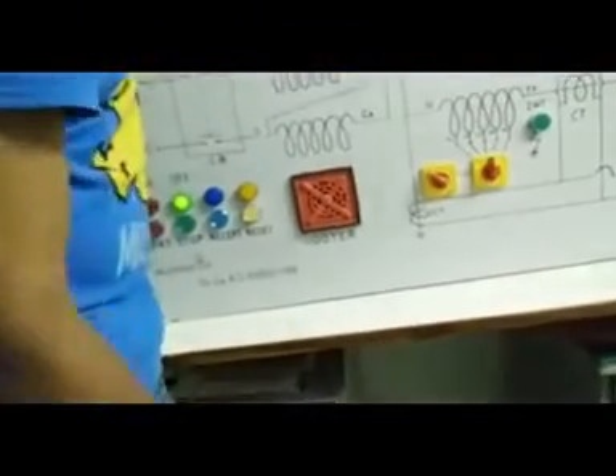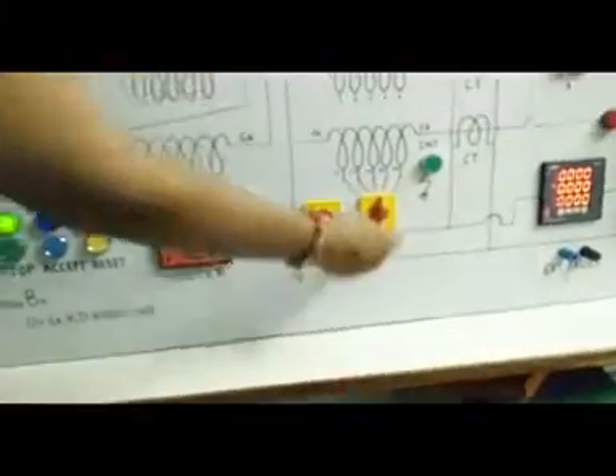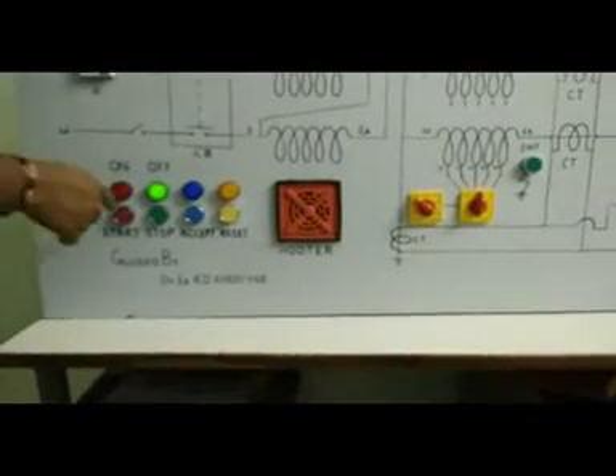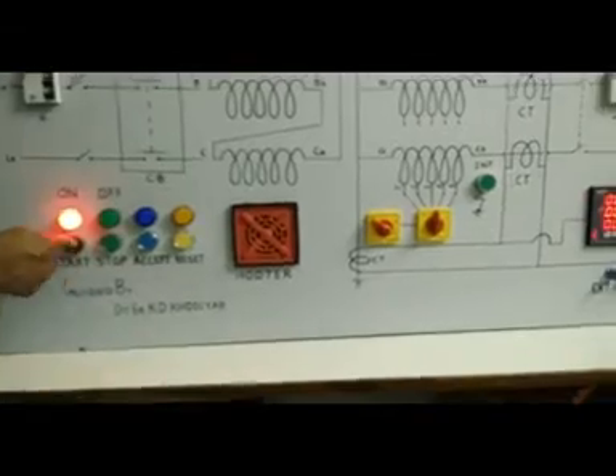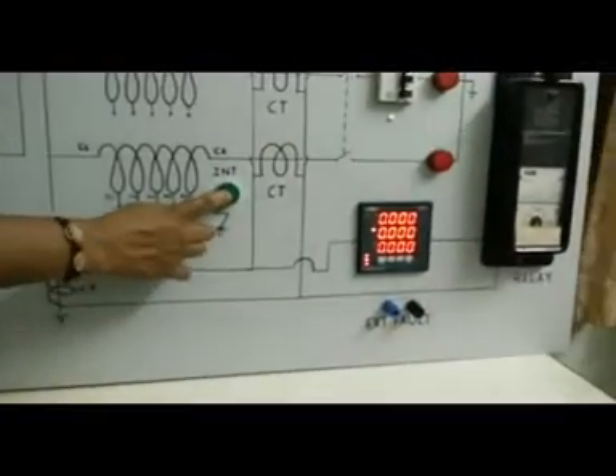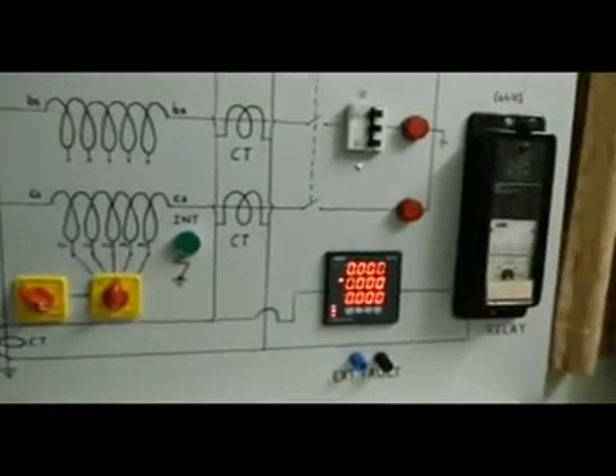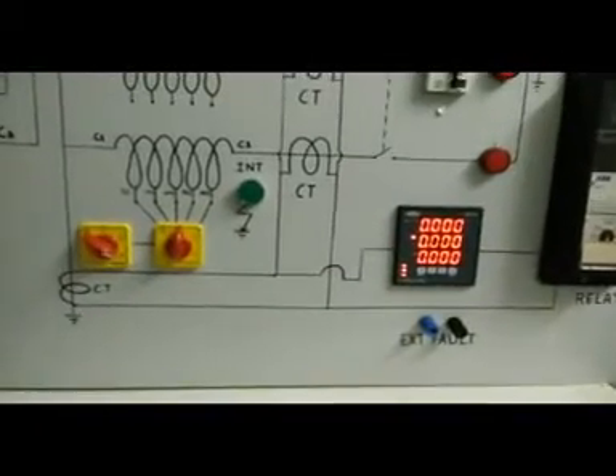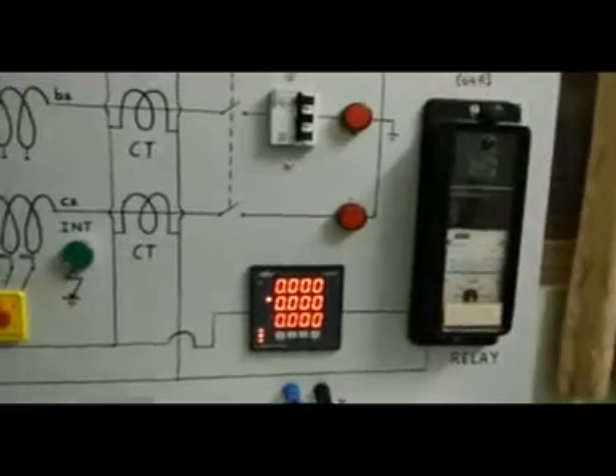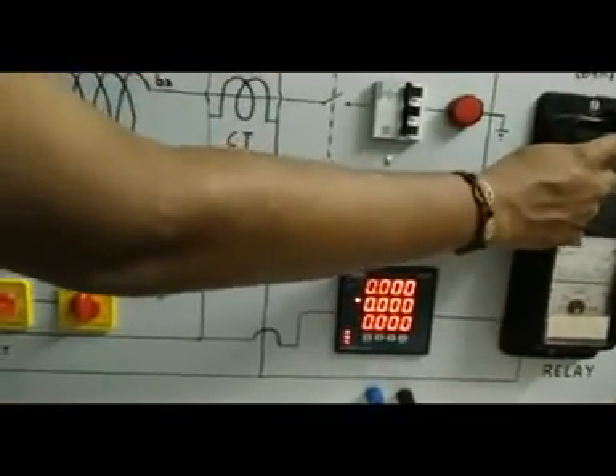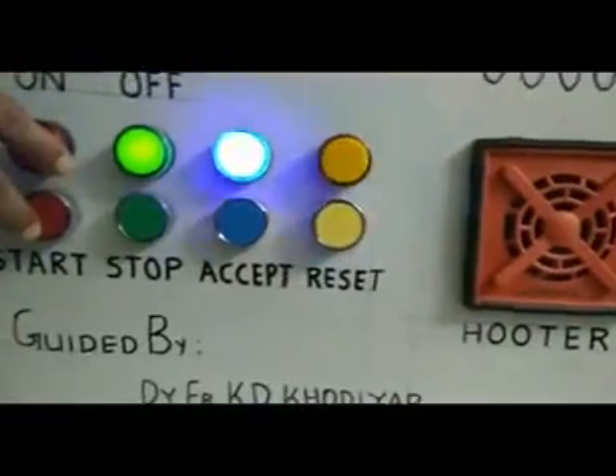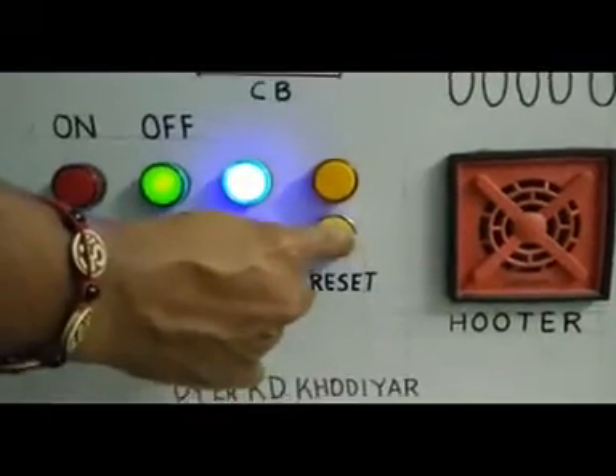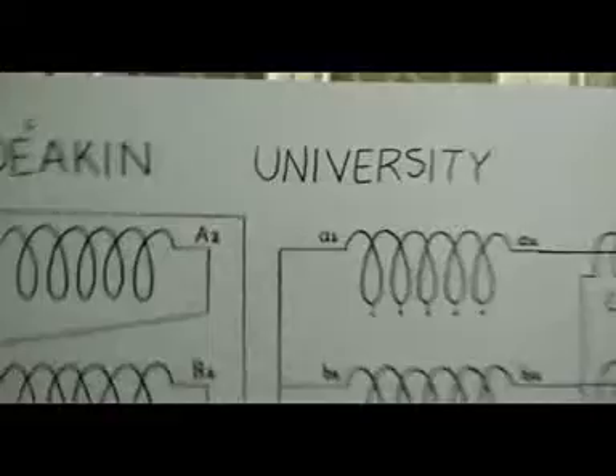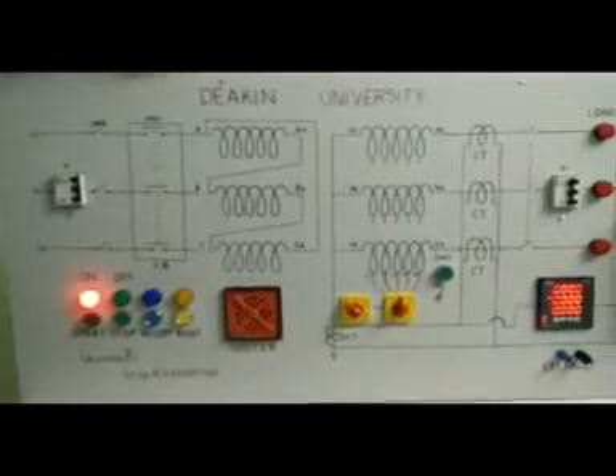And now we'll see the fault at 100%, which is at the end of the secondary, at the last winding of the transformer. So we will again start the protection. We'll generate maximum fault, and we'll see the current is 7.8 amperes. You can see the protection is operated and the fault current is overcome, and we will reset the flag. So reset the fault, reset the system, and again the system is back to its normal condition. So this is the real simulation of restricted earth fault.